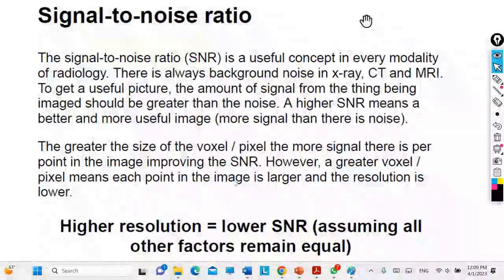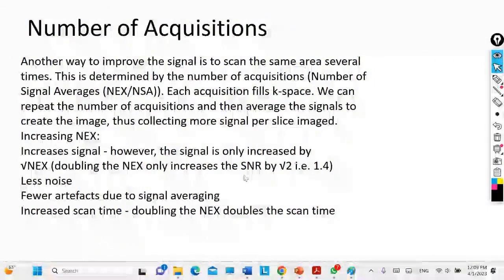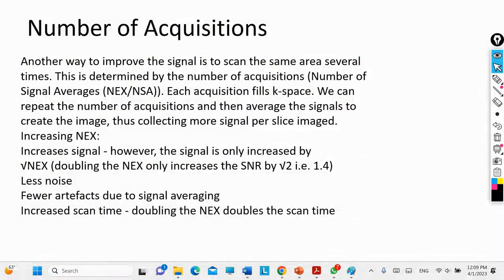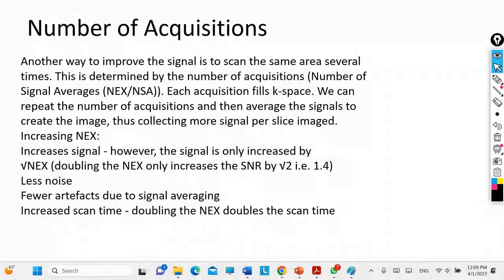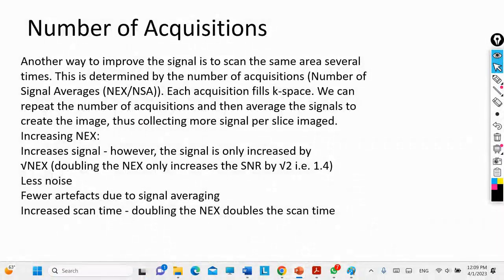There is something called the number of excitations (NEX or NSA). This means you are acquiring your slices more than once. By acquiring the signal multiple times, the signal quality improves. However, this comes at the cost of increasing the scan time. Increasing the number of signal averages increases the scan time but also increases the SNR by enhancing the signal.